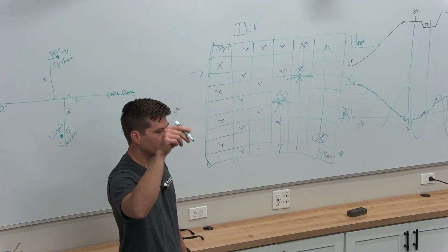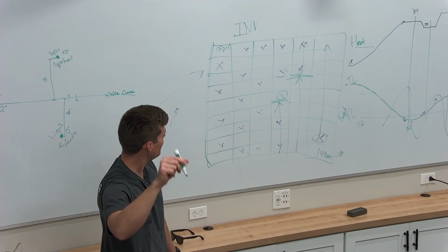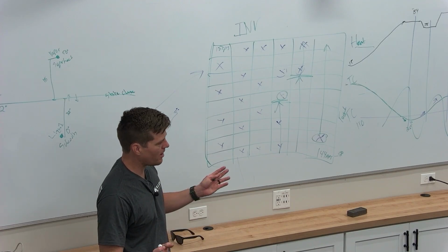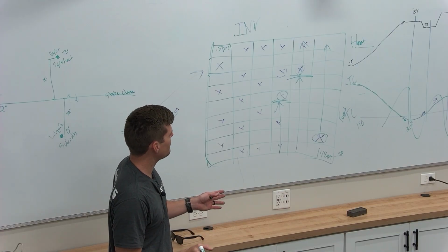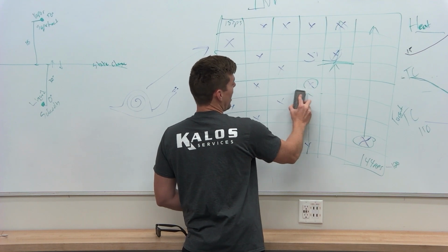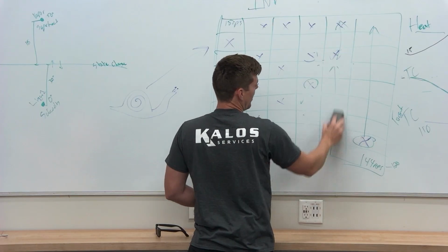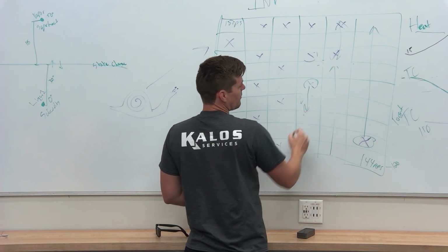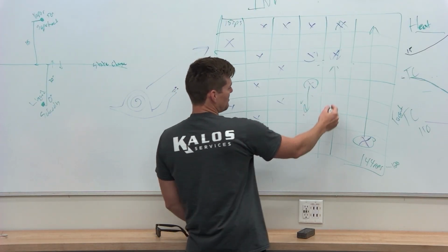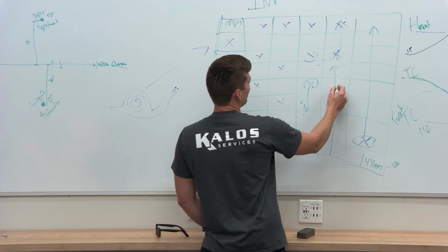And then the discharge temperature will start to fall because it's less refrigerant, it's lower speeds, less friction, and it goes down. And then it'll level off. And it'll say, okay, it came down enough, I'm happy now, it's at 174. So then it'll say, okay, turn off high temp step down, inverter discharge step down. So then the safety controls go away. And now it says, okay, you can ramp up if you want to. And so it's going to try to manage targets again. But then you'll notice that when it gets back up to here, it goes back into step down again because it's 227. And so it says, well, okay, go back, slow down.